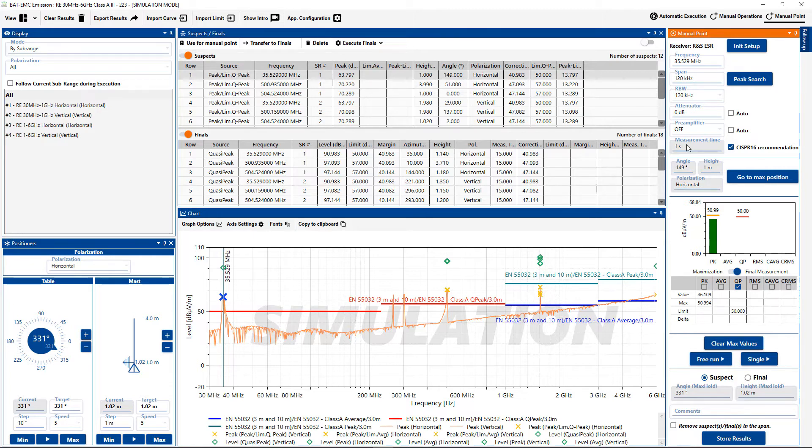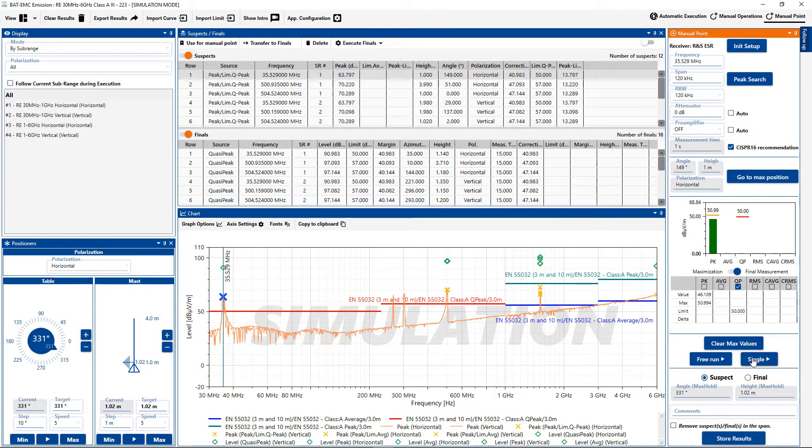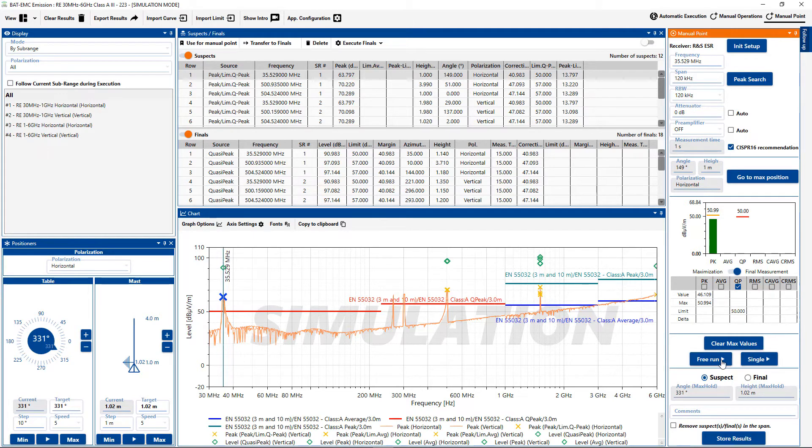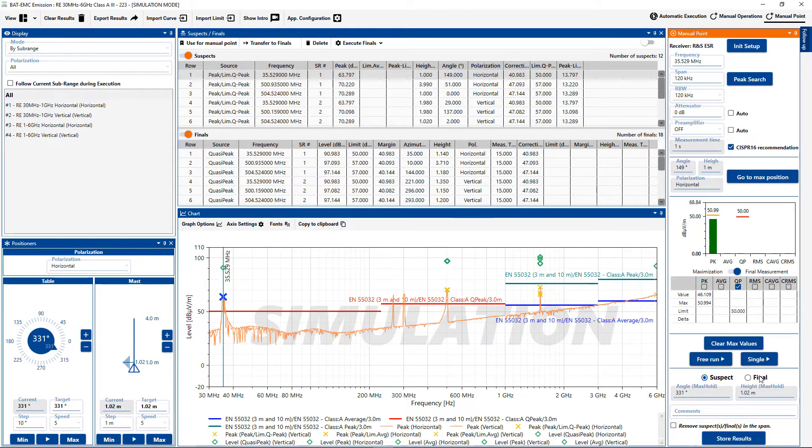And then I can say to do a single run, because that will measure it. It will do a continuous measurement in max hold, and will record that value as the final value after the measurement time expires. The previous measurement in free run would not stop until commanded to do so.